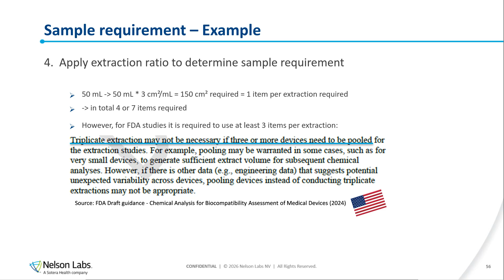And then to close off the sample requirement, I want to quickly talk about item families. It's preferred to test the largest device in your family. So if you, for example, have some kind of plate available in different sizes, it's best to test the largest one. Alternatively, if it's not possible, you can test a smaller device, but then we have to apply a correction factor. And this is easiest done by increasing the clinical exposure.